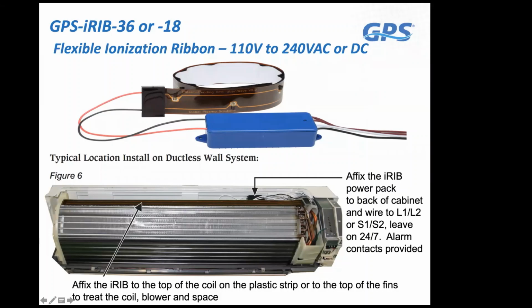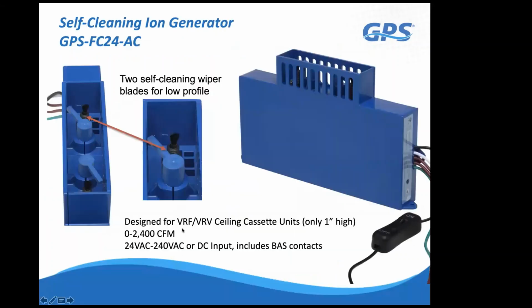It doesn't care what it is. It just senses it and runs. And it's only 2 watts. So we recommend just leaving it on 24/7. That also simplifies your installation and takes away the building control interface to try to interlock it with your fans. Since we don't generate ozone as a byproduct, it doesn't matter that it's sitting here operating when the airflow is turned off. You don't get this huge cloud of ozone dumped to the space because we're not generating it.